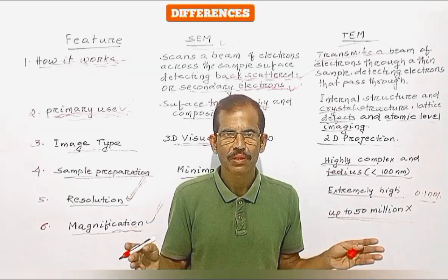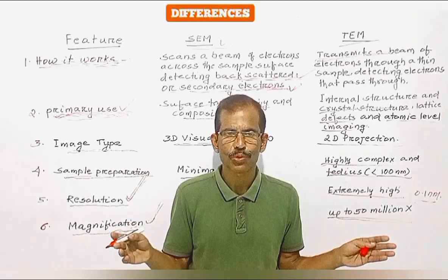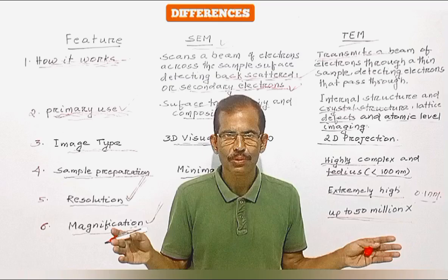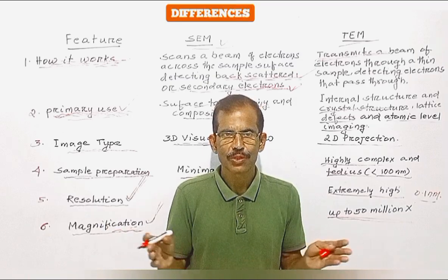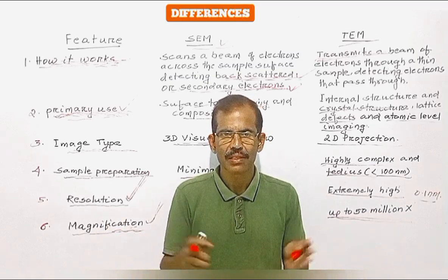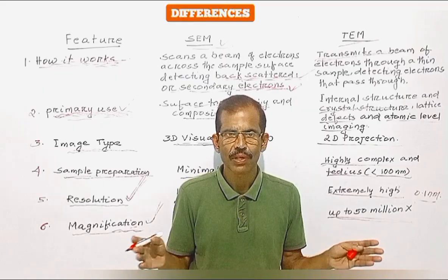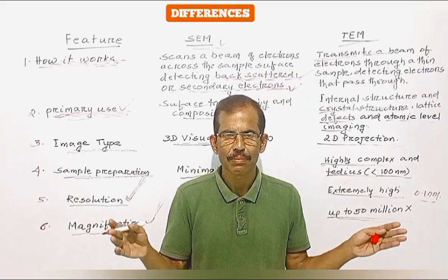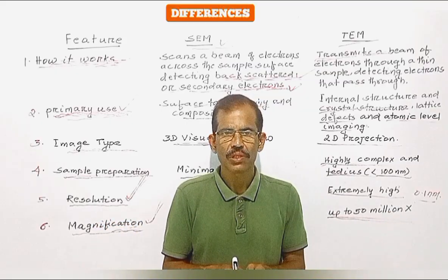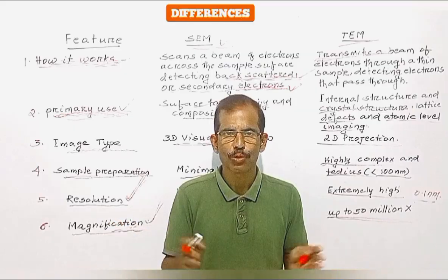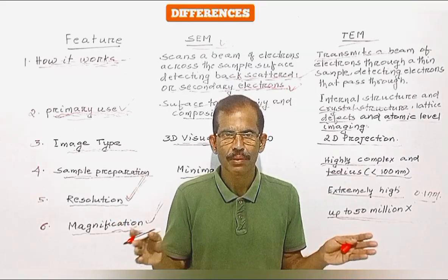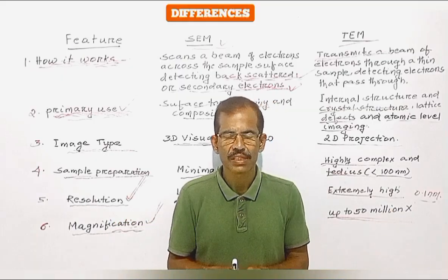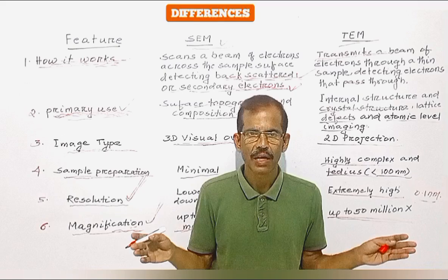The magnification of transmission electron microscope is primarily determined by the current that is applied to the lenses. In such instrument, there are two lenses that contribute to the total magnification. First of all, objective creates an intermediate magnified image which is then further magnified by the projector to form the final image. So friends, this is all about the similarities and differences between SEM and TEM.